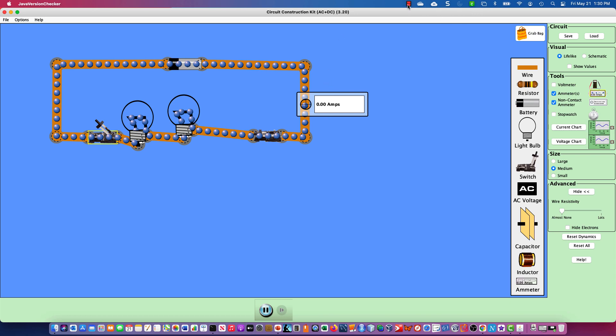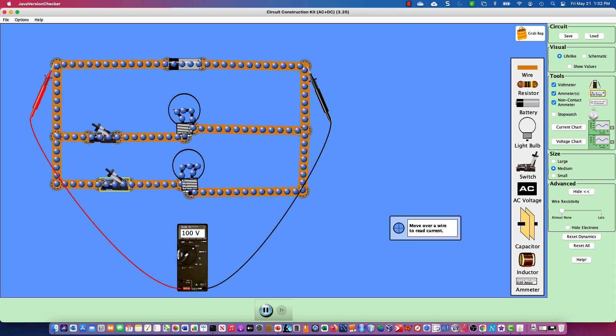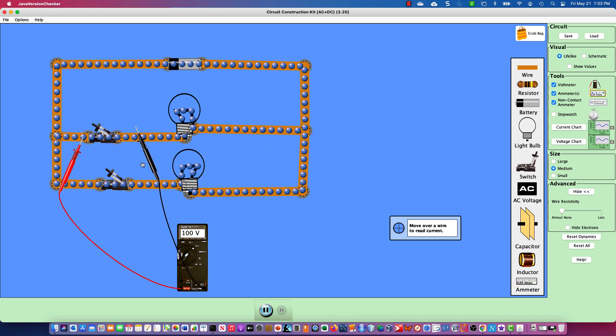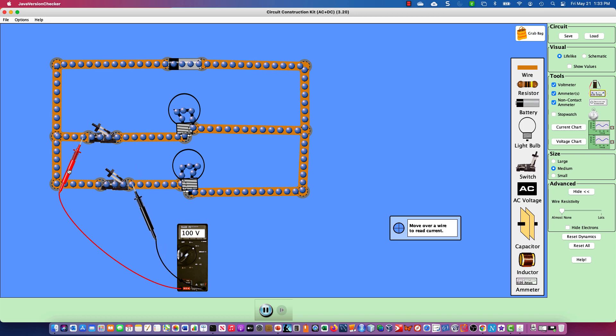Now I'm going to change this to a parallel circuit. You'll see it's basically the same as the slide shown earlier — 100 volts source. I currently have two switches open. If I take a voltage across each side of a switch, I have the potential of 100 volts across those switches, because an open switch will always read source voltage on your meter.